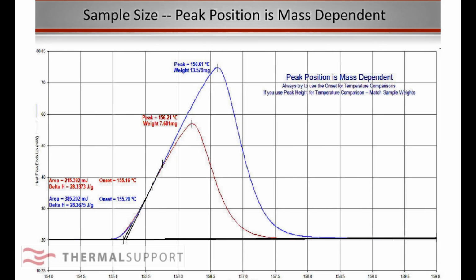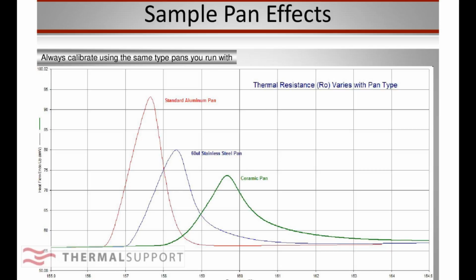Same thing with sample size. If you're calibrating with a peak, you need to make sure that you start matching your masses up when you're doing your calibration. If your typical sample is say 10 milligrams, you want to have a 10 milligram reference material also. And then sample pan effects. Remember, you want to make sure you use the same pan to calibrate with that you use for your sample.